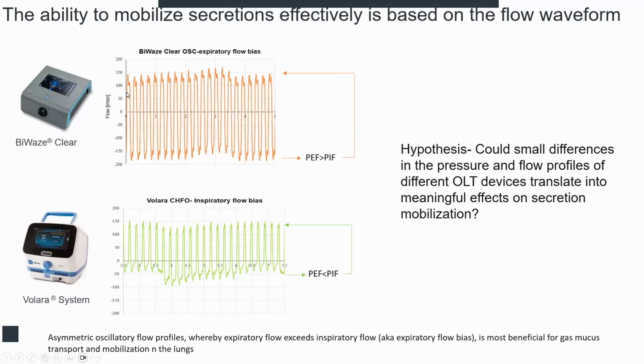So with the BiWaze Clear, you're getting an inspiratory flow which is going to be slightly greater than a lot of the other devices. It has a dual blower design, provides slightly higher pressures. What you said is kind of what you get, right? Whereas with some of these other devices that incorporate a single limb circuit and they have a fairly large leak because they don't have an expiratory pathway, then they have to exhale their CO2 to air, much like BiPAP. Then what happens is you lose a lot of the pressure through the system. But in these devices, what we've recognized is that the peak expiratory flow is less than the peak inspiratory flow. And so we think that could be important because in this case, the expiratory flow is higher than the inspiratory flow. All right, enough about that.